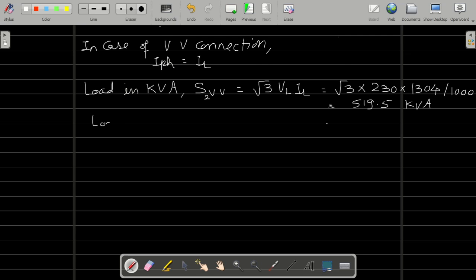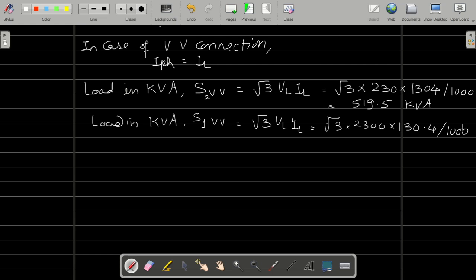Similarly, load in kVA on primary side, S1 for VV connection, same formula √3 VL IL. √3 VL is the primary side voltage, that is 2300. IL is 130.4. Divide by 1000 to get kVA, and you will get the same answer, 519.5 kVA.